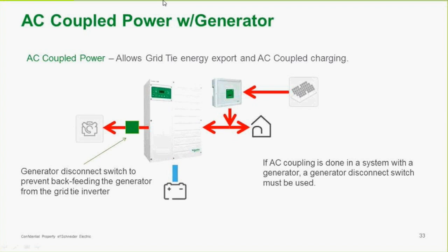And here we have AC coupled power with the generator. Now this is a little bit different. We can't actually have the generator connected at the same time that the AC coupled grid tie inverter is charging the system, because any AC that might get fed back to the generator is a dangerous thing. So there needs to be a disconnect switch here that keeps the generator disconnected when there's PV production from the grid tie inverter.